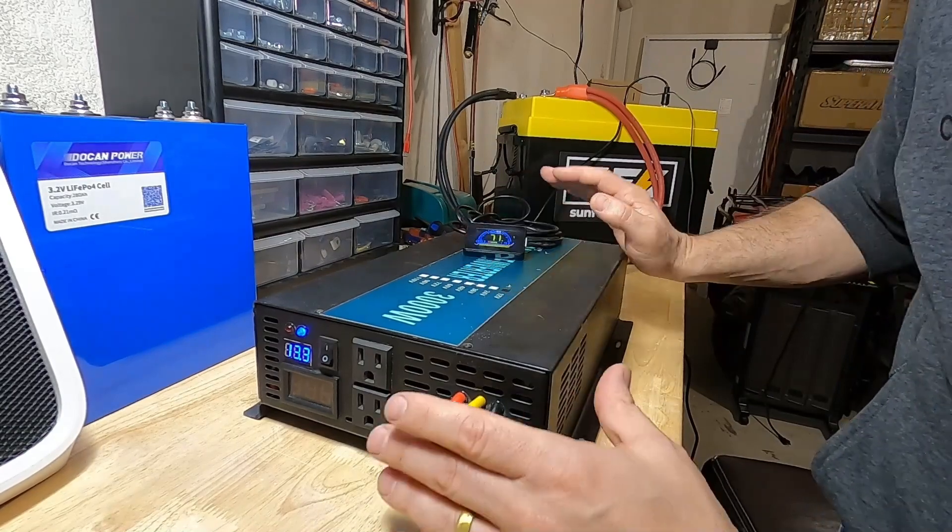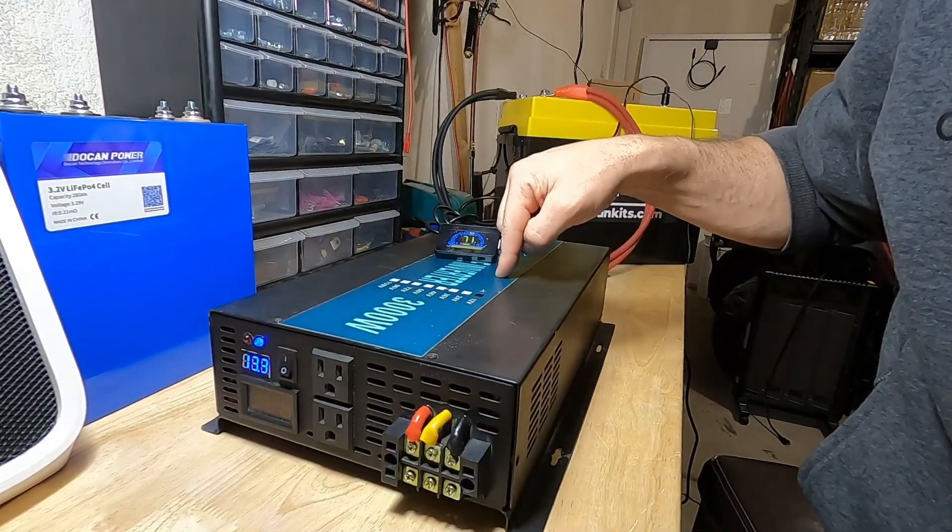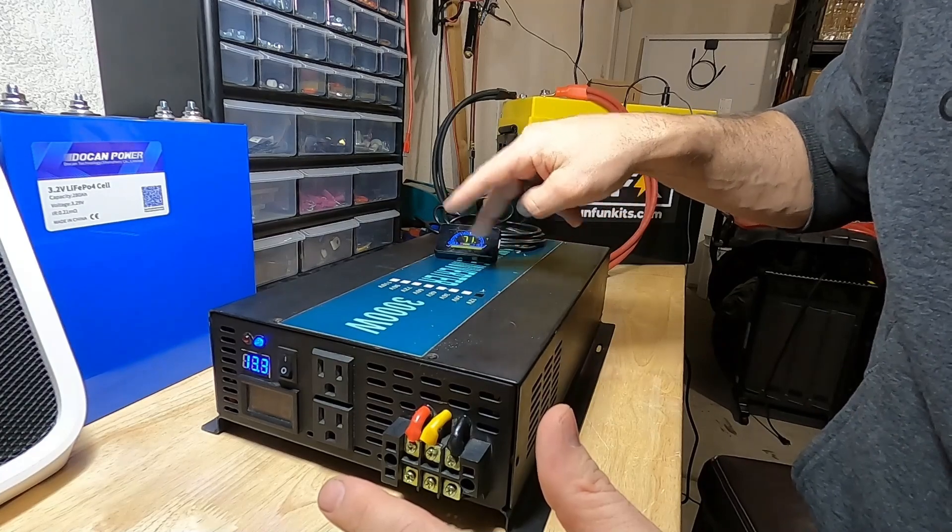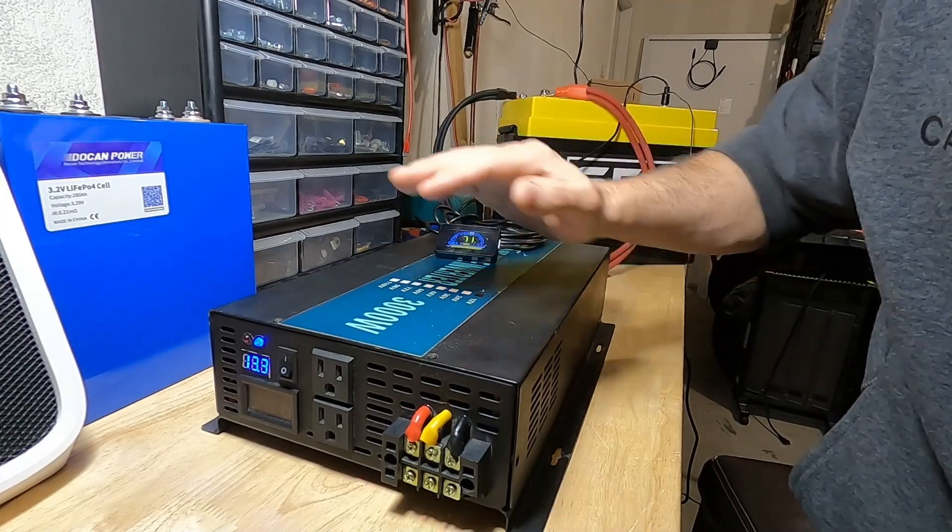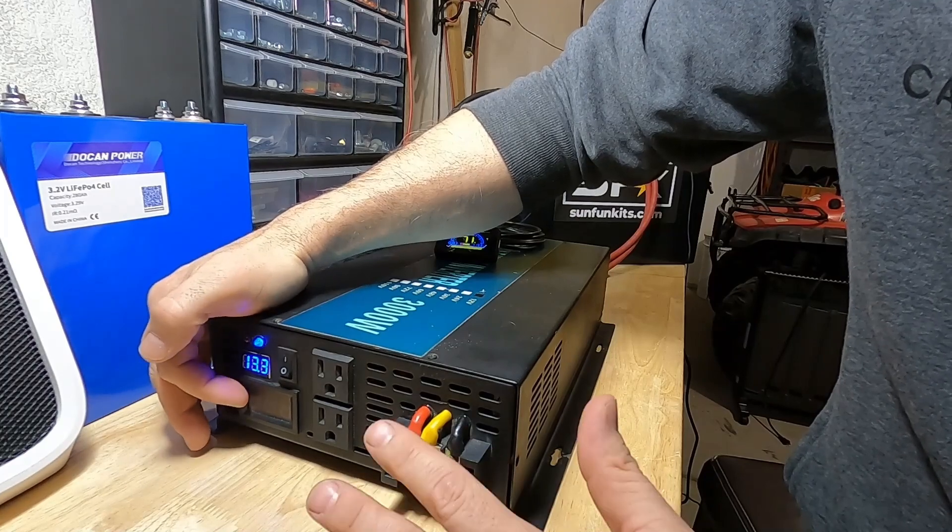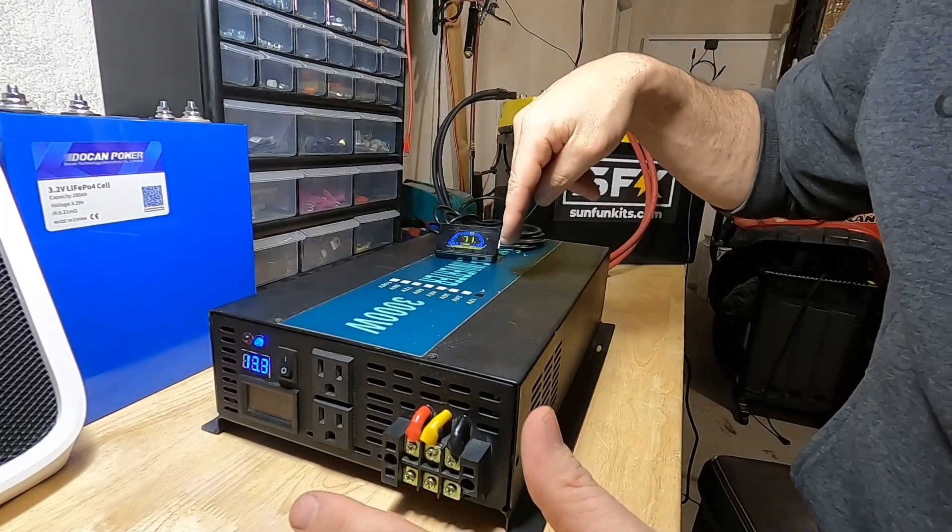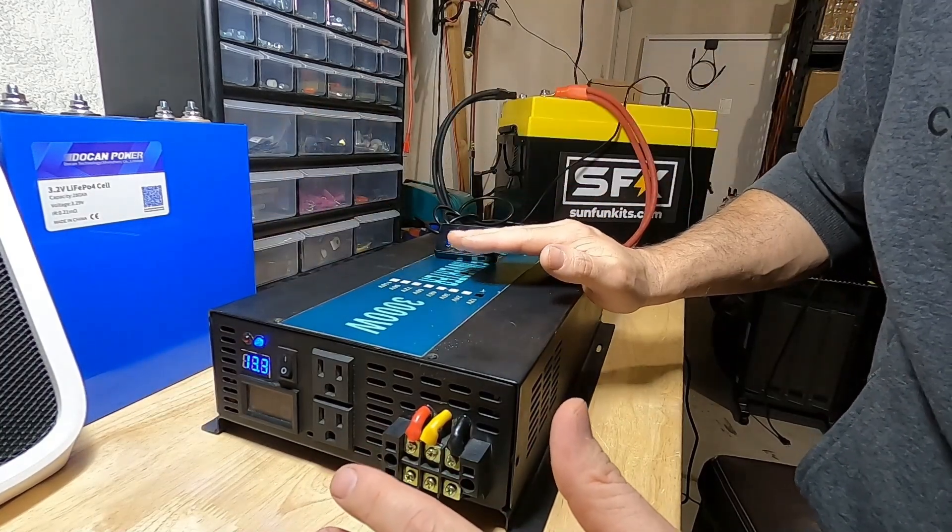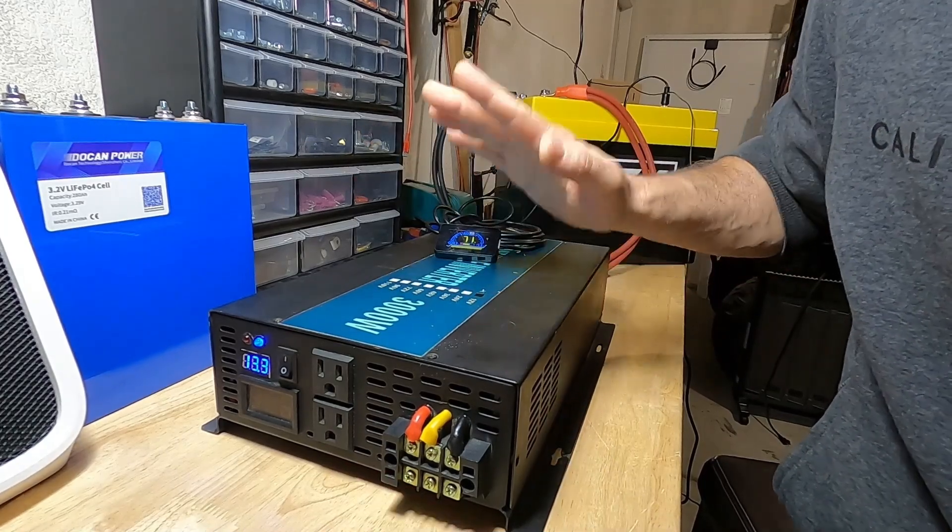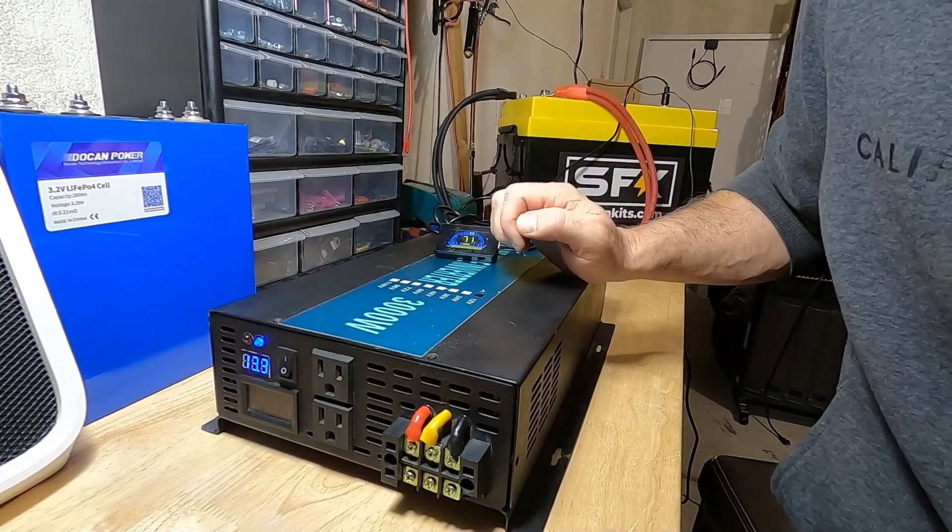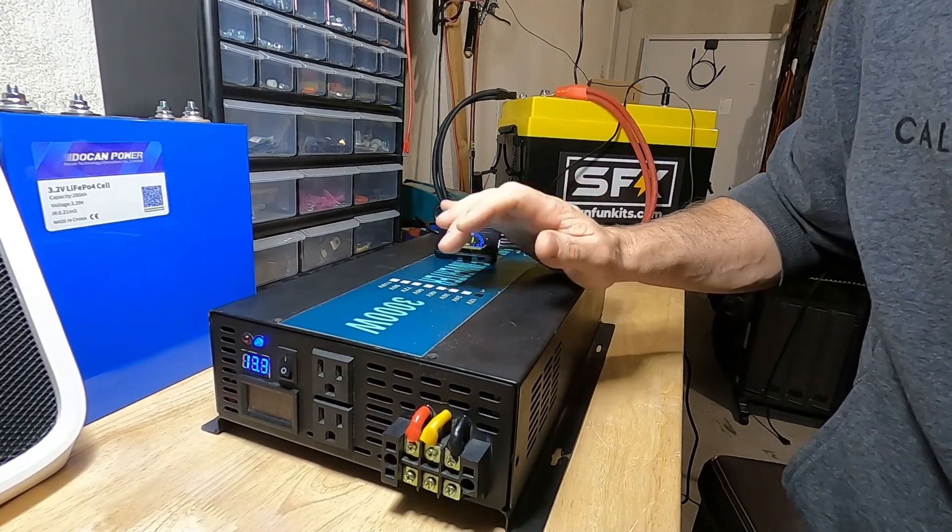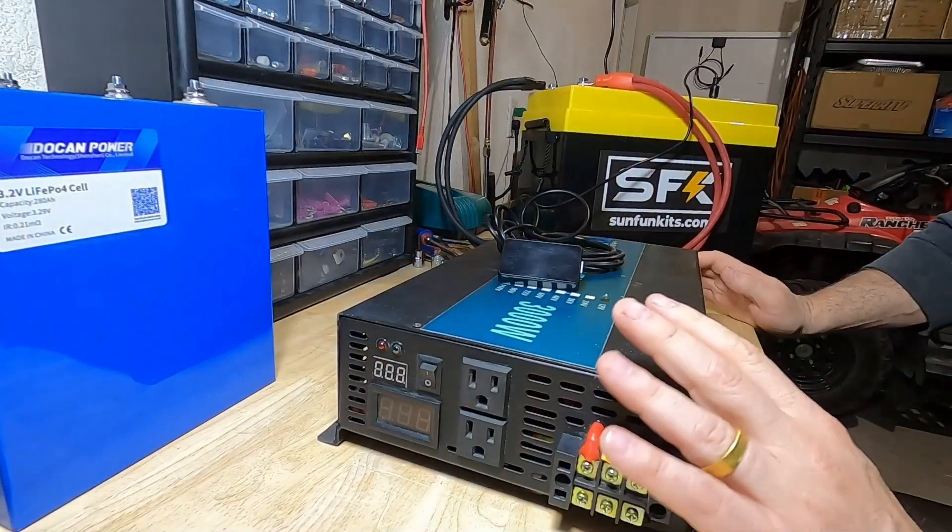What that means typically on these inverters: there are eight fuses inside in pairs of two 240-amp fuses in parallel. For this display to not read any output, one pair of those fuses has to be broken. If one fuse is broken, the inverter will still operate to about 160 amps. Very likely there are two fuses blown in this inverter.